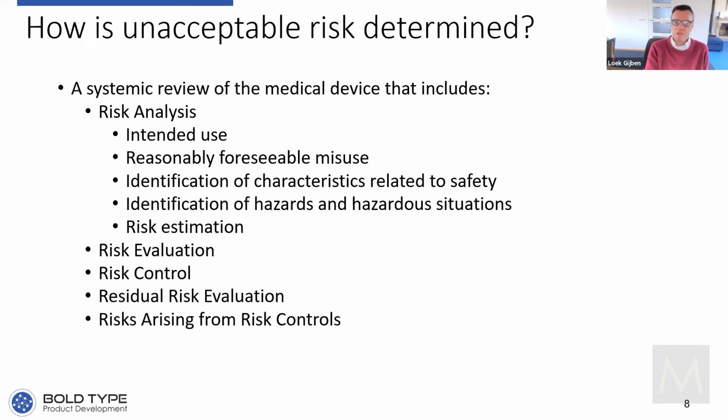And that's nice to know, because a lot of meetings go about reasonable foreseeable misuse. And also, sometimes if you do a risk analysis, you come up with really remote risks, and you have to try to mitigate them. We always say, are you willing to use the device on your mother or not? And if you're willing to use it on your mother, it should be safe.